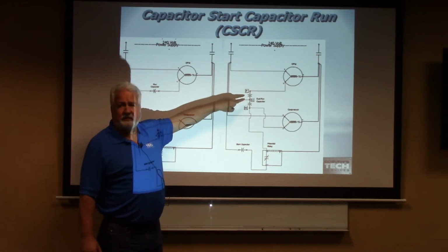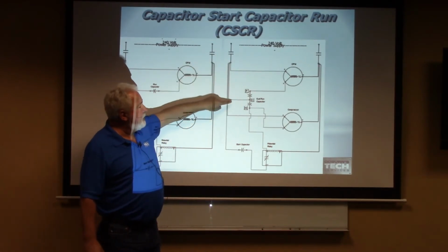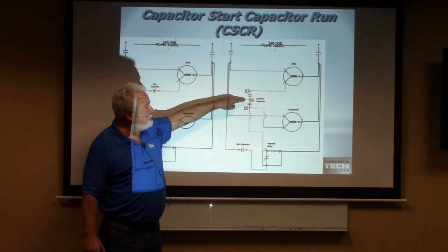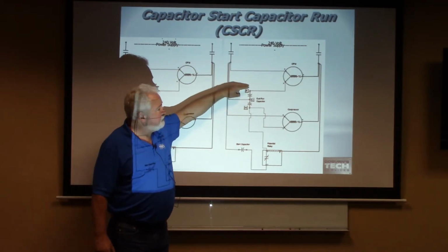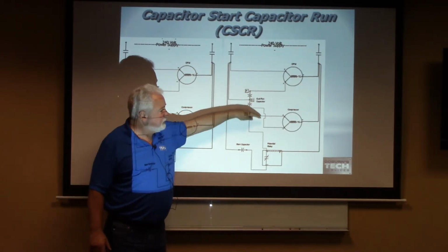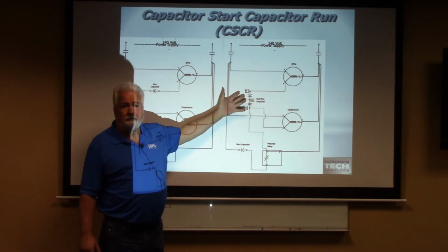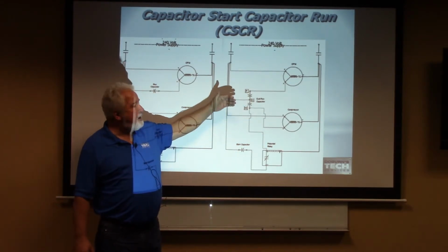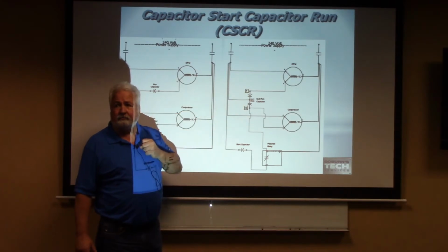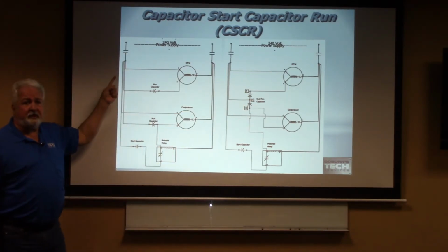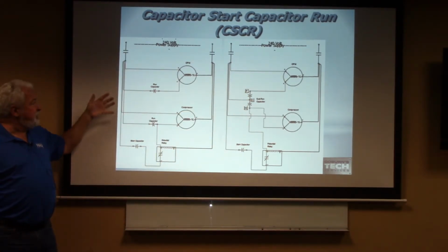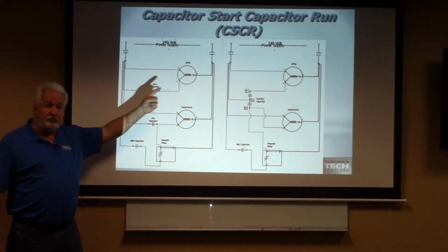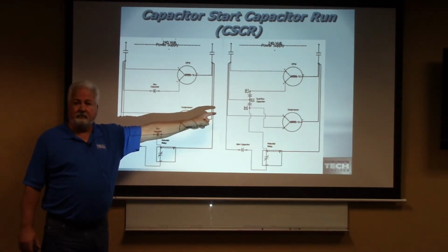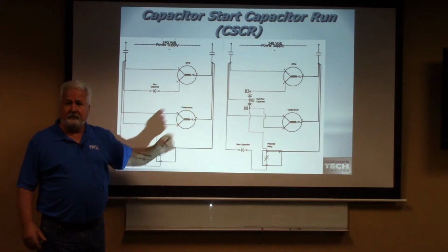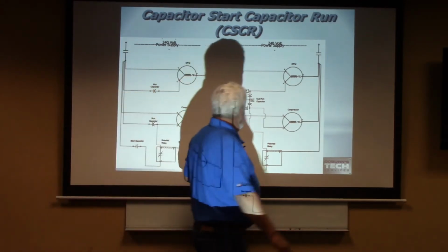This is a dual capacitor. Comes from the line to the common side of the dual run capacitor, then it goes to the fan, and it goes to the compressor. Anything wrong with that? Can I take a dual out and put two singles in? Can I take two singles out and put a dual in? Absolutely can. Is everybody okay with that? Good.